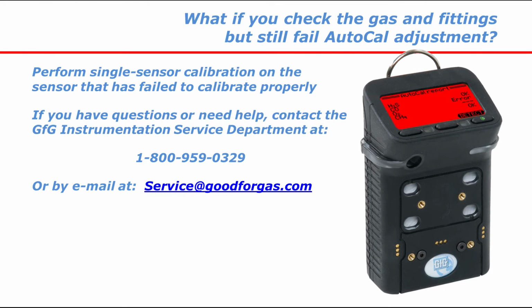Autocal adjustment is designed to handle the minor adjustments that need to be made to the sensors on a normal day-to-day basis. Occasionally, instruments are exposed to chemicals or conditions in the atmosphere that can harm the sensors. Sensors that have lost sensitivity due to exposure to poisons or inhibitors may require a larger calibration adjustment than is allowed during the autocal procedure. To make large adjustments, it is necessary to use the service menu to make a single sensor calibration adjustment.